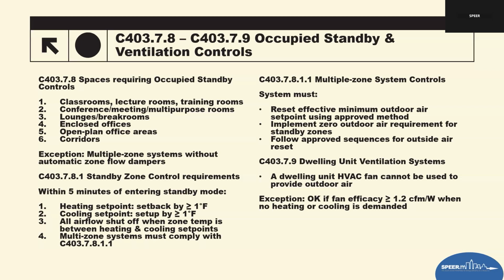A heating and cooling fan system, like blower in a split system, cannot be used as the outdoor air unless its fan efficacy meets the 1.2 CFM per watt under no load conditions. So this prevents inefficient blowers from being used and to provide continuous ventilation. Kind of the same thing that residential has, is that fan efficacy table that air handlers must meet the same requirement, the 1.2 CFM per watts.